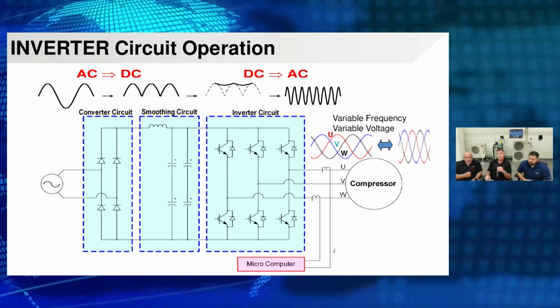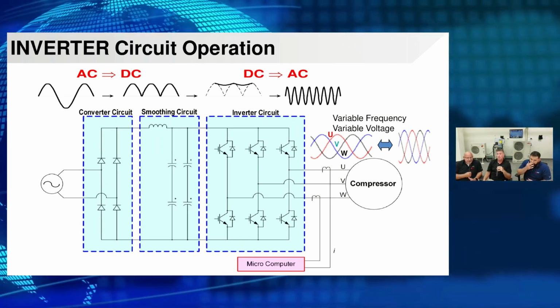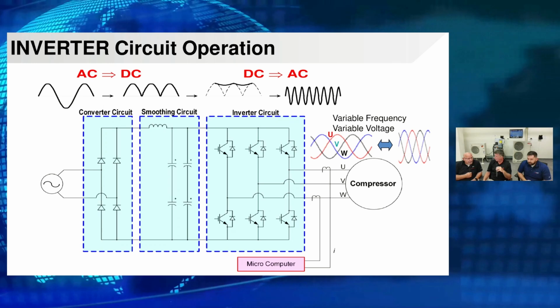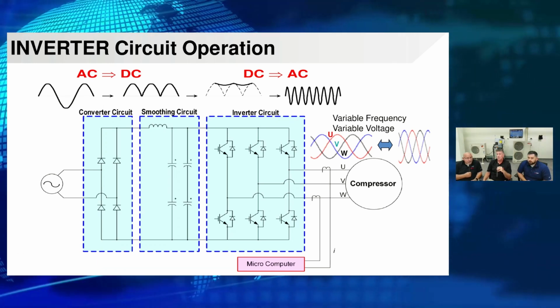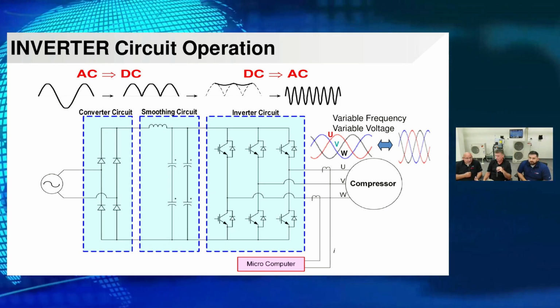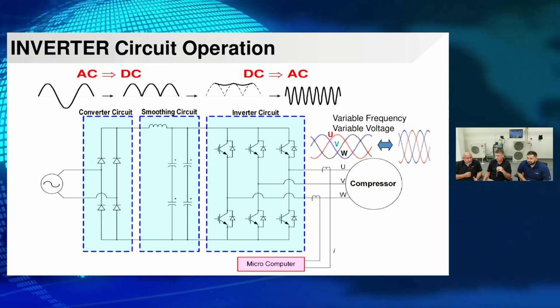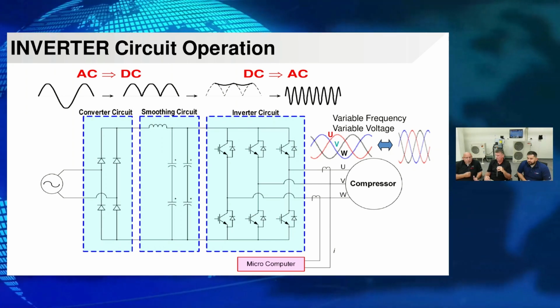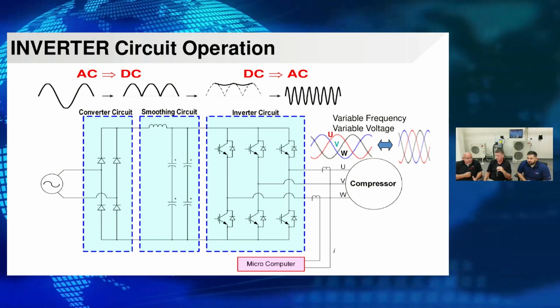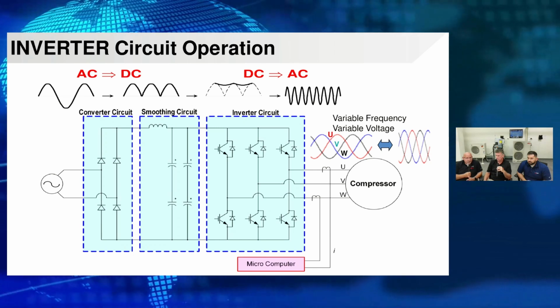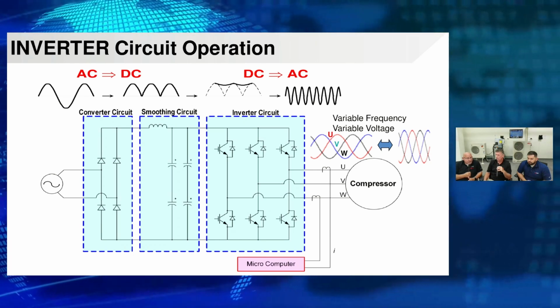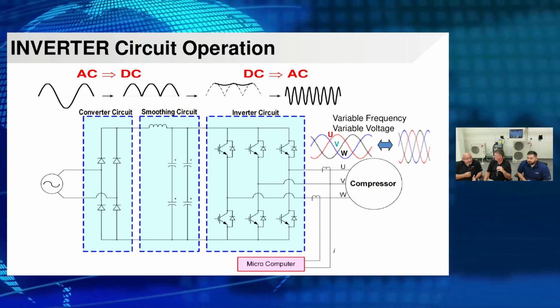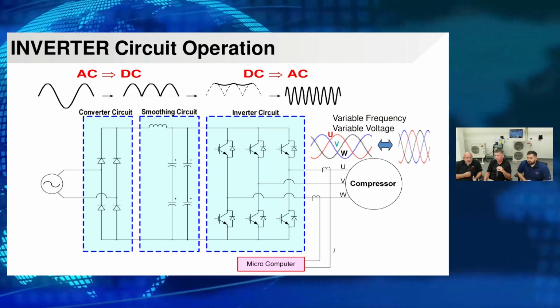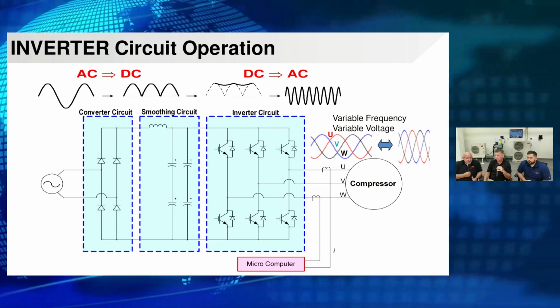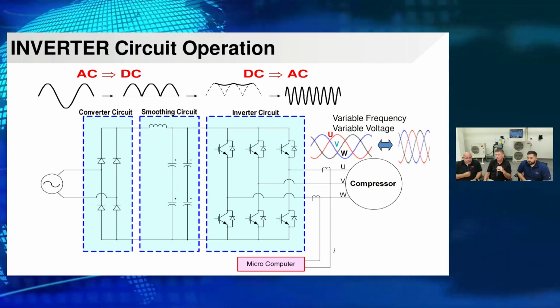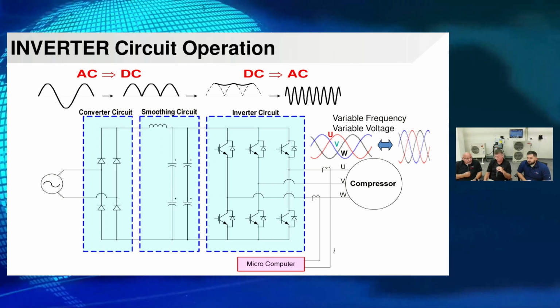Here's what we have: a generic inverter circuit. Electricity 101 - we have the source, which is the electrical supply coming into the outdoor unit, incoming AC. We have the path, which is all the circuit boards. And ultimately we have the compressor or motor, which is the load. That's electricity 101. So let's start at the source. In this scenario we have 208 or 230 coming into the outdoor unit, single phase.